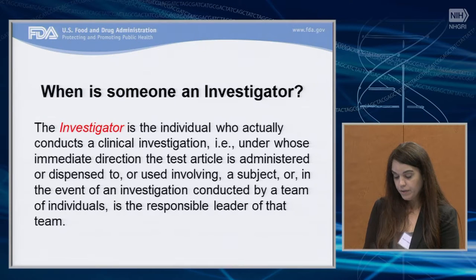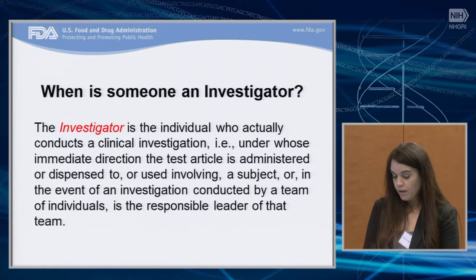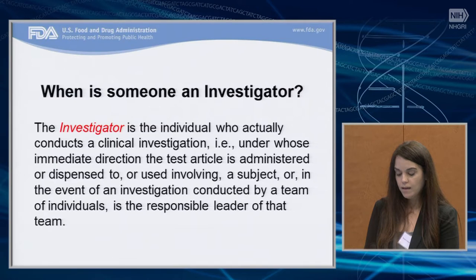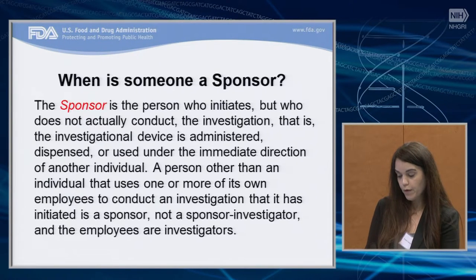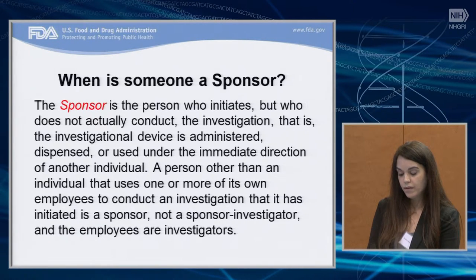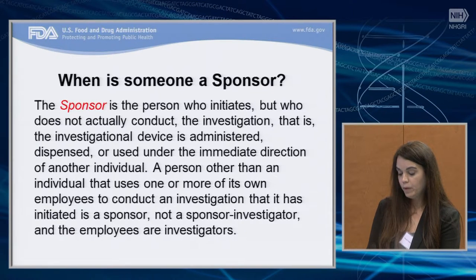The term investigator is defined in the IDE regulations as the individual who actually conducts a clinical investigation — that is, under whose immediate direction the test article is administered, dispensed, or used involving a subject, or in the event of an investigation conducted by a team, is the responsible leader of that team. The investigator does not initiate the study. This is different from the definition of a sponsor. The term sponsor is defined in the IDE regulations as the person who initiates, but who does not actually conduct the investigation. A person other than an individual that uses one or more of its own employees to conduct an investigation that it has initiated is a sponsor, not a sponsor-investigator, and the employees are investigators.